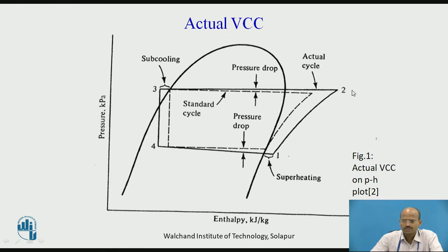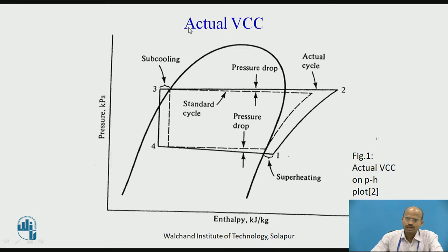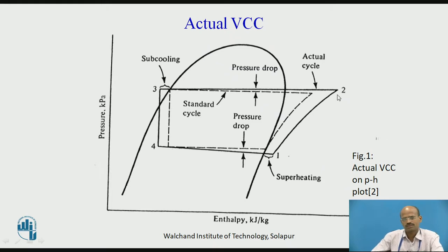So superheated vapor will enter into the compressor, which will get compressed actually. Here, 1 to 2 is the actual compression process, while for theoretical VCC the compression was isentropic. For actual VCC, it is an actual compression process, and depending upon the specific heat, there will be a corresponding value of the compression index. Point 2 represents the actual compression process, so at 2 a more superheated vapor refrigerant is leaving the compressor. For theoretical VCC, the exit refrigerant temperature was at a lower point, so there is more superheating caused due to practical considerations.